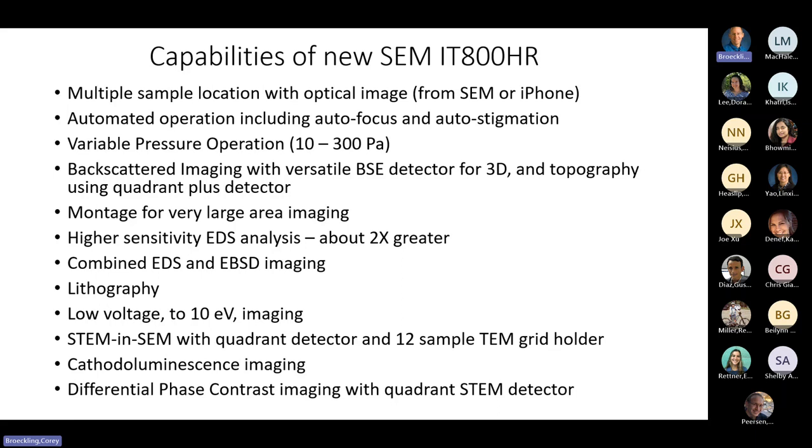One of the big pushes is low voltage imaging, down to 10 eV imaging. That's substantial. Now, we'll see how well it works, but that's what they claim. The big thing that I'm excited about is DPC, differential phase contrast imaging, which can be applied to things that have different electric or magnetic fields. And we will have cathodoluminescence, which is pretty exciting too.